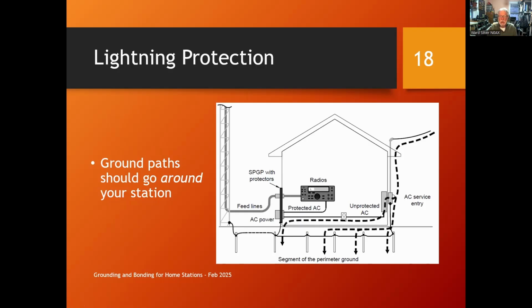This is the branch circuit that you run all the way over to your single point ground panel, and you've got a protector over here. Okay, so that protector helps the lightning go outside and find your perimeter ground. So it sees this great, terrific, heavy, direct path to the earth outside your house, okay? And it doesn't want to flow through your radio station on the way to the ground. Give it this big, heavy, direct outside path.